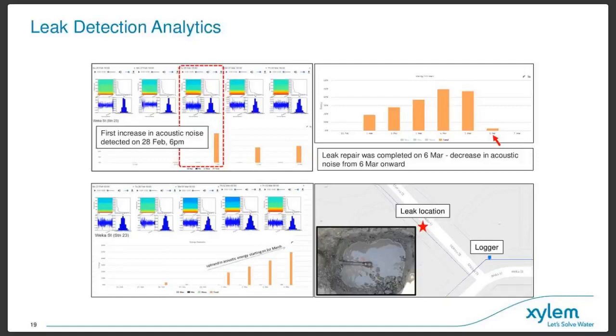And you can see here an example where the noise has increased, and then the leak has been identified and then repaired, and the validation of the repair can be seen by the drop in the acoustic noise.